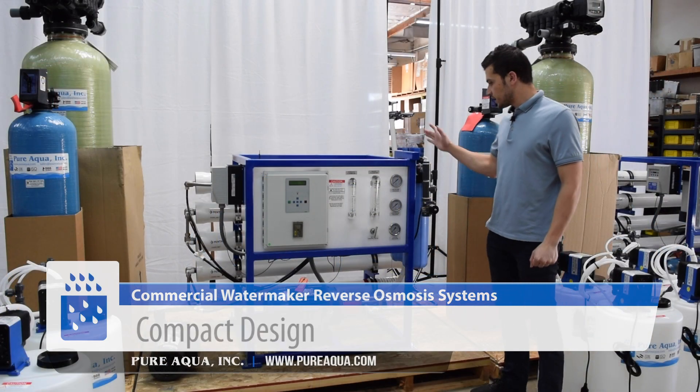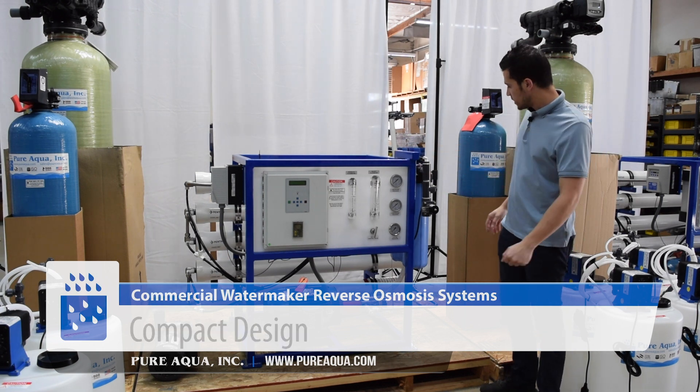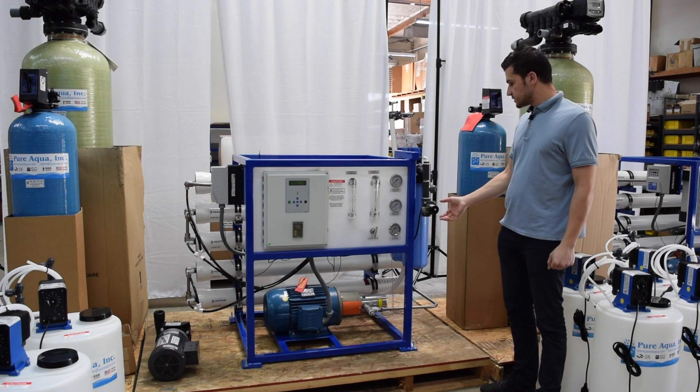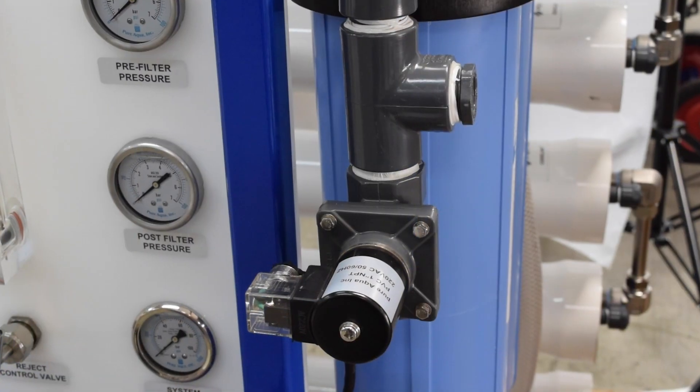This very compact seawater RO system comes equipped with many different options as shown here. Starting from the feed side, we have a PVC inlet valve and an injection port for the anti-scalant, followed by 25 and 5 micron cartridge filters.